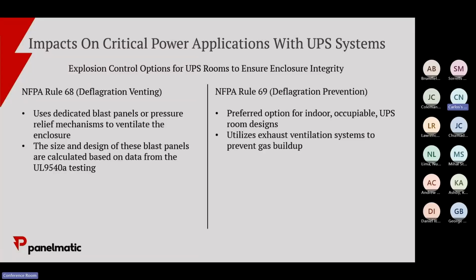This is where you get into gas detection and ventilation, basically circulating the air in that room to keep the threshold below 25% LFL. Inside these spaces they'll use a gas detector that picks up VOCs, hydrogen, and a few other things, plus an airflow meter. You put those sensors at the bottom and top of the racks, and the idea is you move enough airflow through the room to keep that level below 25%. If it starts to exceed that after a certain threshold, it'll just open the doors.